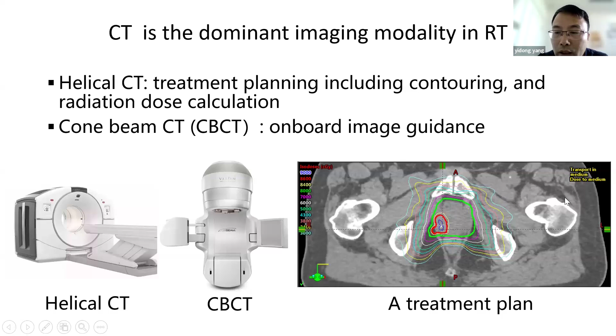So just briefly, let me talk about the difference between fan beam CT and cone beam CT. I think fan beam CT is based on sectional imaging. That means we image the patient slice by slice. Now we also have volumetric imaging because most scanners can provide multiple row detectors, like 64 rows and even 320 rows. So now it's more like volumetric imaging, but usually we call fan beam CT section by section imaging. But cone beam CT is volumetric imaging because one single shot can provide one projection of the entire volume. We use a flat panel detector for image acquisition. So usually we just need one single rotation for imaging the entire patient volume.